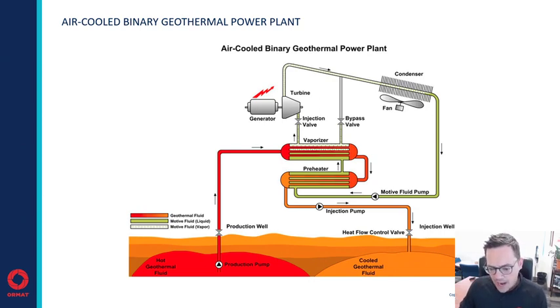The geothermal brine, on the other hand, moves through the preheater as it starts to cool down, and then we inject it back into the geothermal reservoir. It matriculates across the hot rocks and cracks and permeability in the Earth's surface and warms back up again until we pull it back out at the production well. So the geothermal fluid is also in a constant loop, only meeting the working fluid for a moment in time in the vaporizer and preheater.